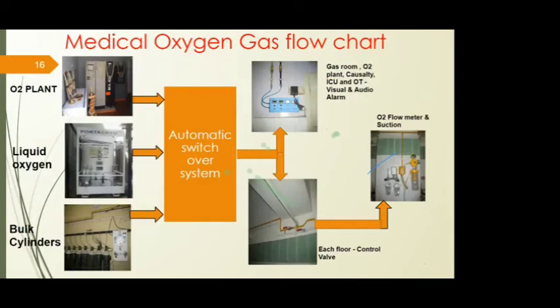It will be connected through a chain, so these three things will go to one automatic changeover panel. From there, any one source can be connected. Whenever the alternate source is not working, if the liquid oxygen is not there, then the gas flow will come from the O2 plant. I've shown the indication for alarm as well as visual indication. These should mandatorily be there in the gas room, O2 plant, casualty, ICU, and OT - these are the mandatory places.